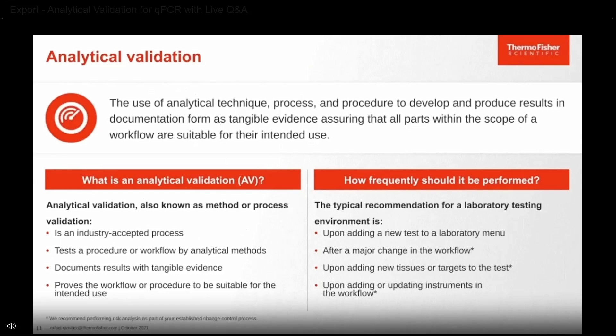Let's recap on what an analytical validation is: the use of analytical technique, process, and procedure to develop and produce results in documentation form as tangible evidence, assuring that all parts within the scope of a workflow are suitable for their intended use. How frequently should you be performing a validation? Any time you're adding a new test to your menu or making a major change within your workflow — changing sample types such as urine, tissues, or swabs, or adding a new assay to your panel.